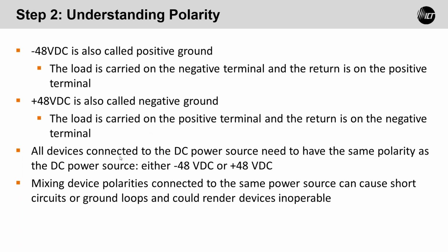It's got the load on the plus side and the return on the negative side. Keeping in mind that all the devices connected to the DC power source need to have the same polarity as the DC power source, so it's either neg 48 or plus 48. The important thing is to avoid mixing polarities connected to the same power source. That's where you let the smoke out, and that's what we really want to try to avoid.